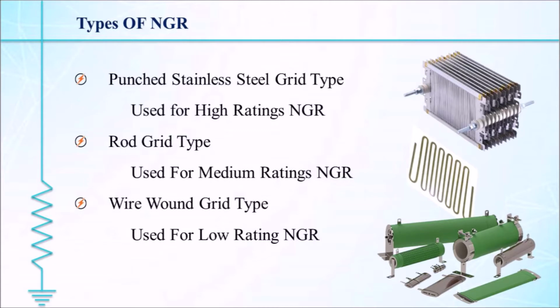Now I will explain how the classification of NGR is done. The classification of NGR is done according to the ratings: punch stainless grid type, rod grid type, and wire wound grid type. Punch stainless grid type is used for high rating NGRs, rod grid type is used for medium rating NGRs, and wire wound grid type is used for low rating NGRs.